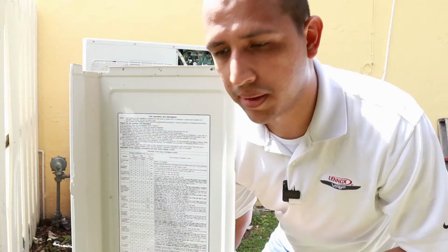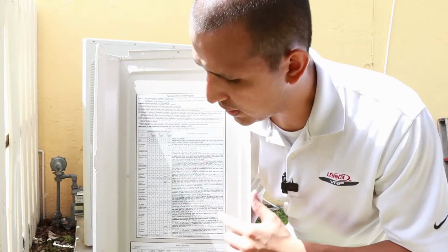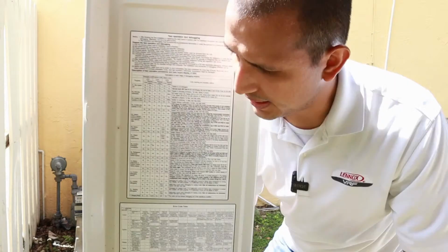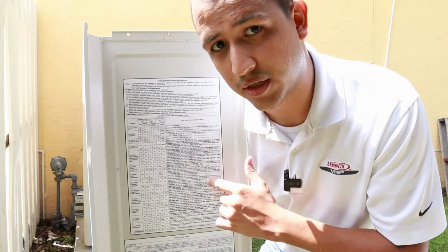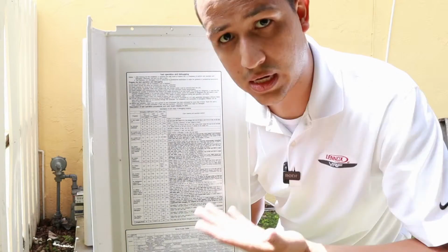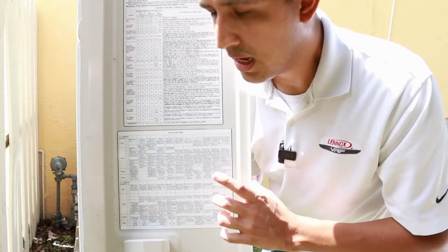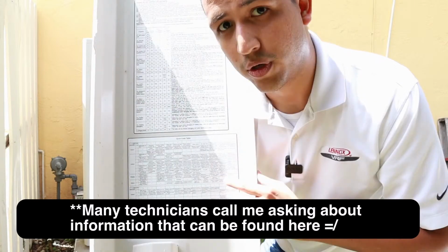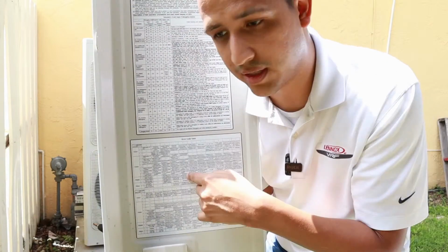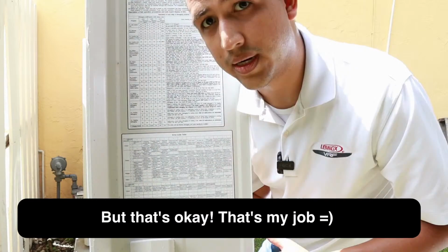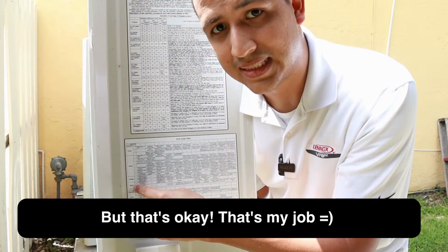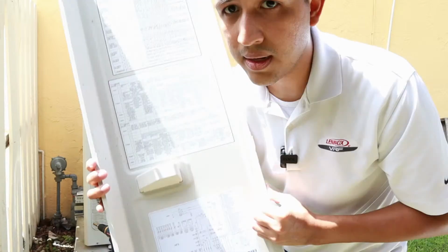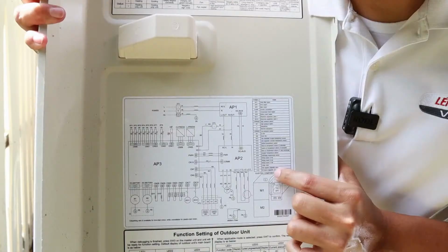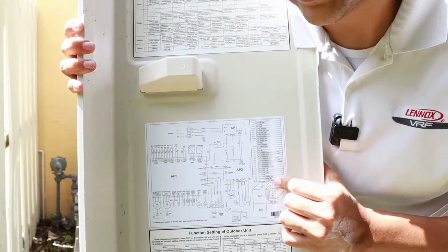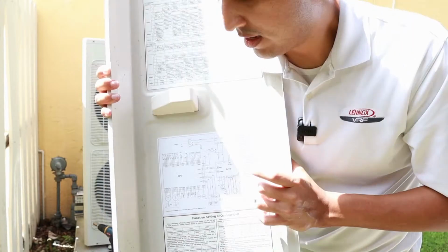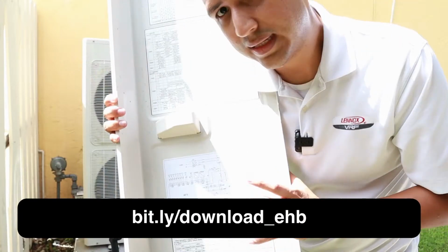Something very important to keep in mind. On the back of this panel, we have different stickers, different labels that I want you to keep in mind. At the top are the steps for the commissioning cycle. It walks you step by step on how to perform the commissioning cycle. The second sticker is actually a table for error codes. Notice it has indoor unit and outdoor unit codes, and also, when you're doing a commissioning cycle, status codes. At the bottom, we have the wiring diagram that I always recommend to take a picture of, although you can find this in the engineering handbook, but it's always nice to keep it handy.